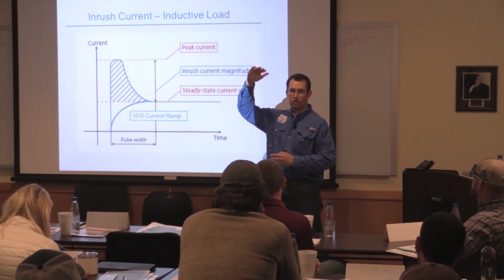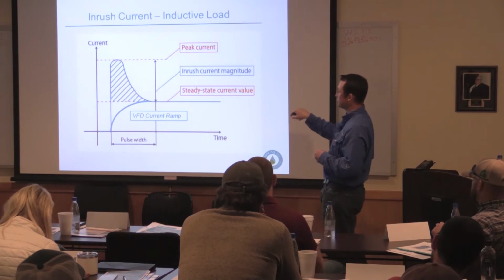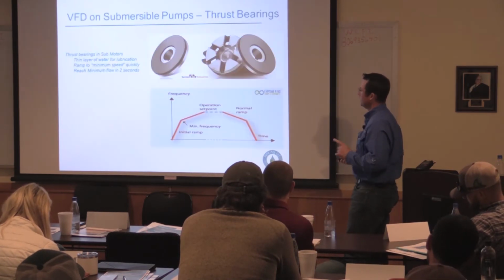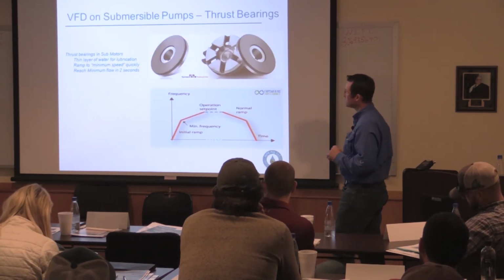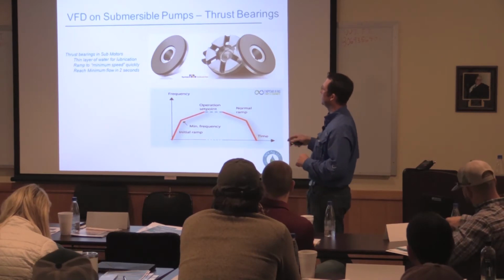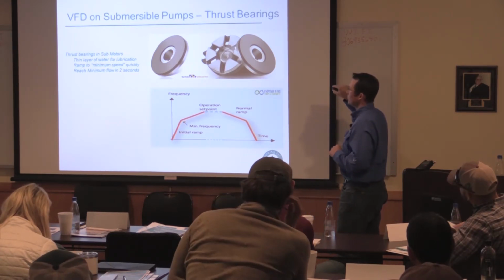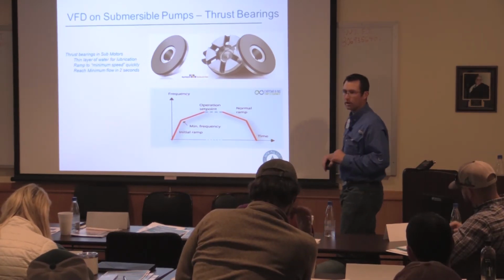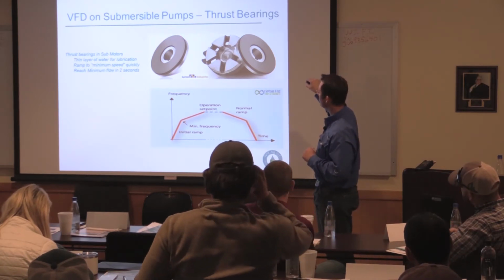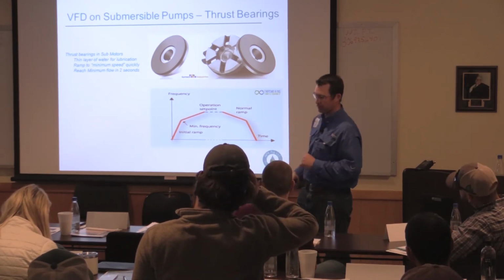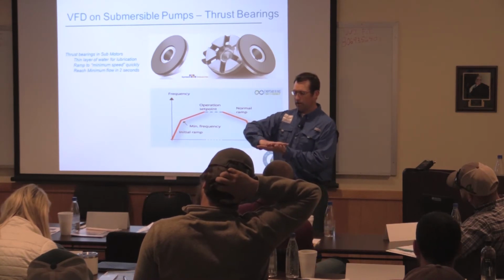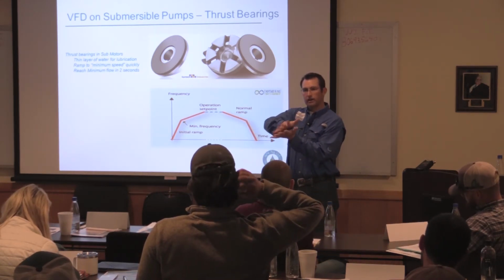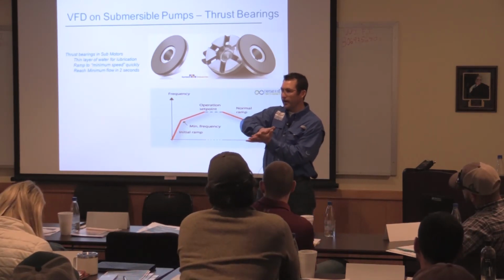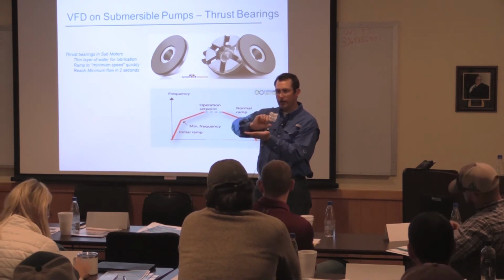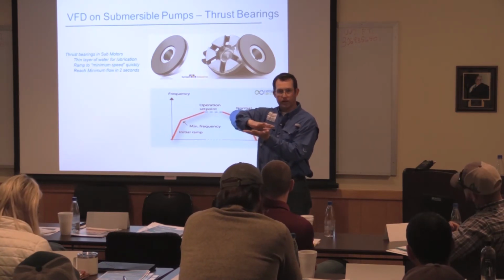It's actually flowing water. So keep that in mind. You can ramp up to that with control. There's a couple of caveats when you're talking about submersibles and drives, and these are very important. Modern submersible motors use thrust bearings that are water lubricated. Okay, so these are the friction surfaces on them. And by a thrust bearing, what it's doing is that bearing is basically riding on itself.